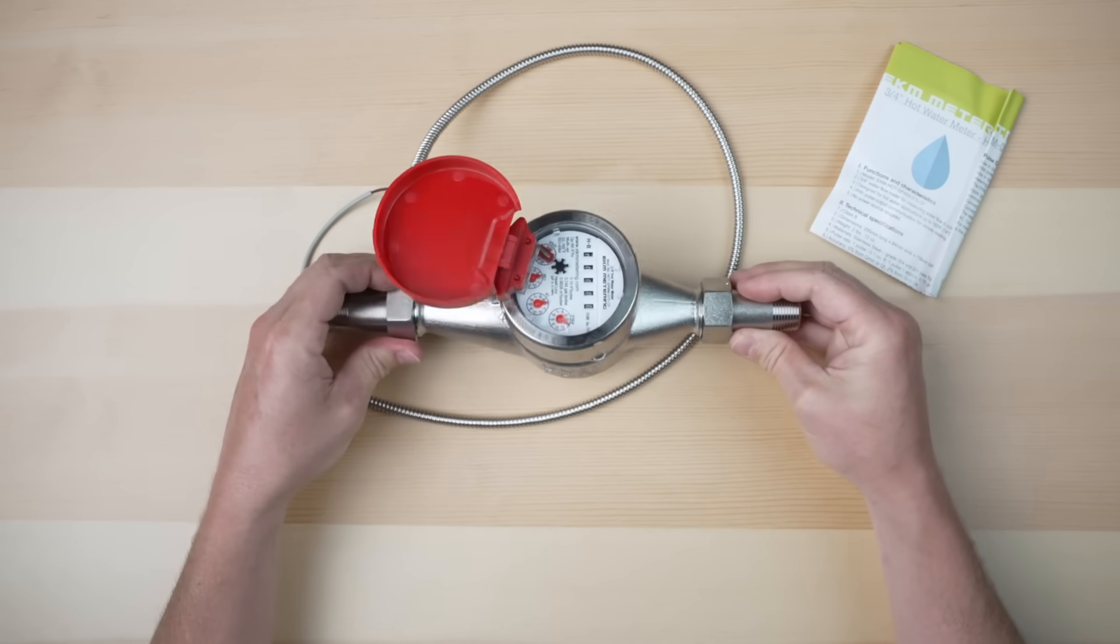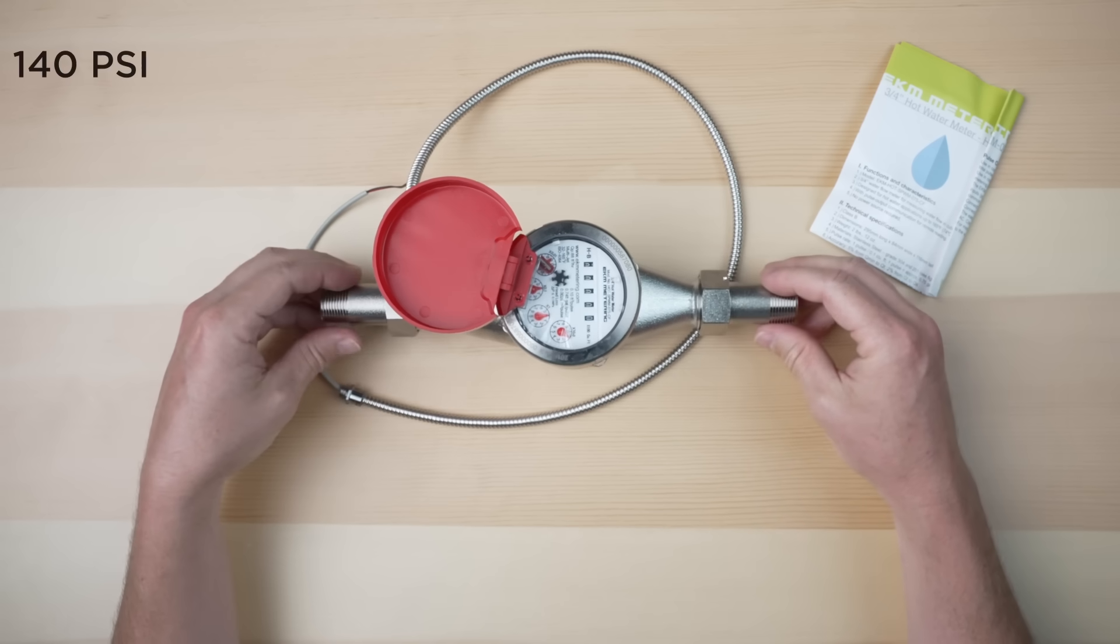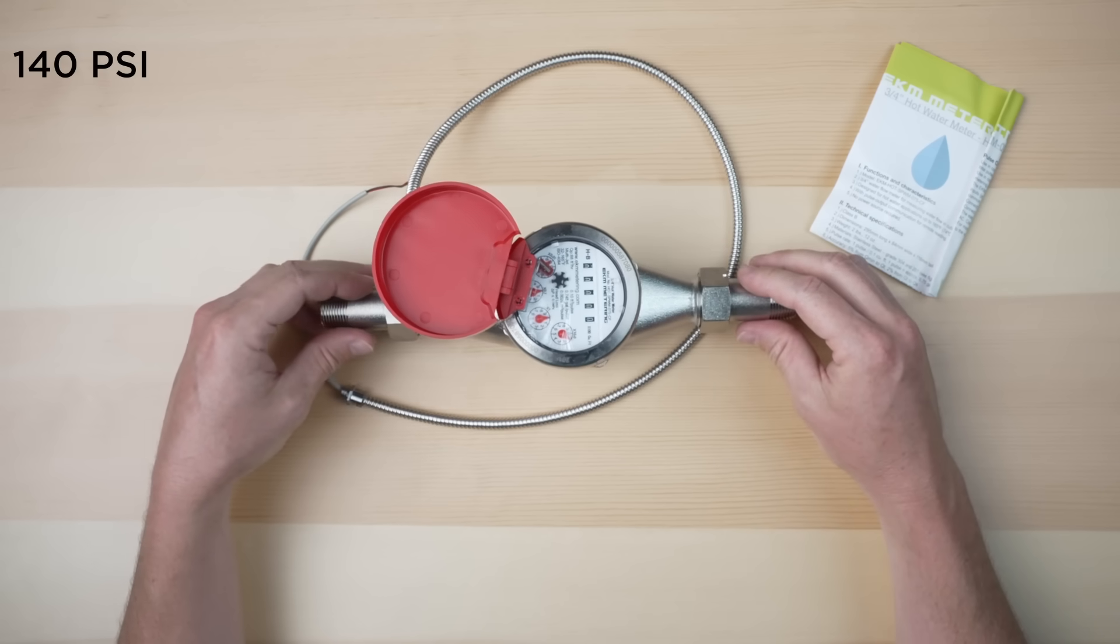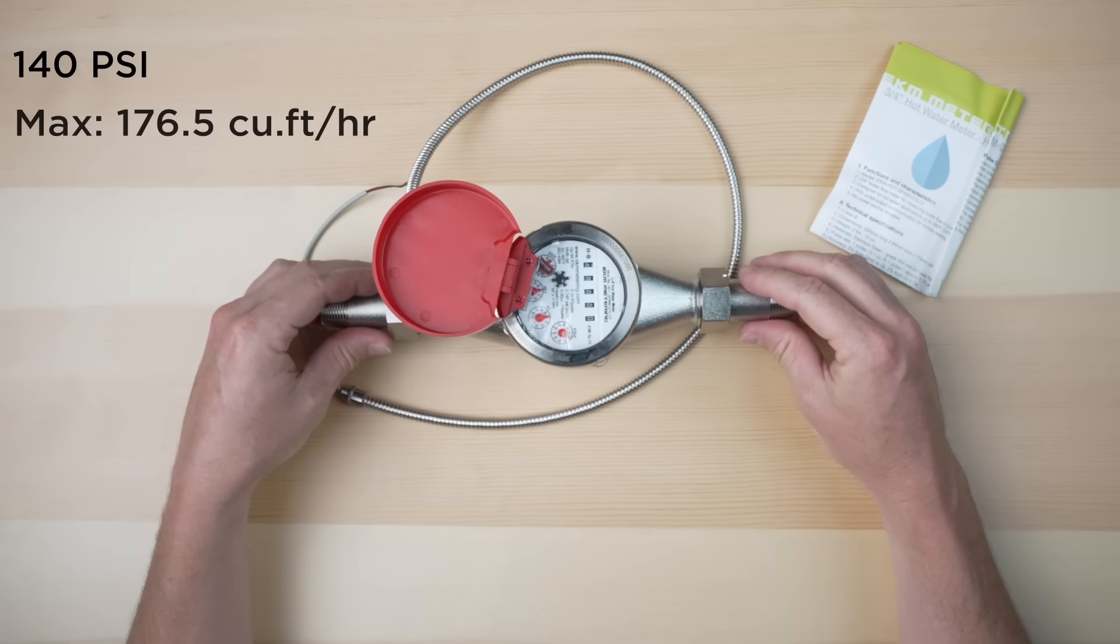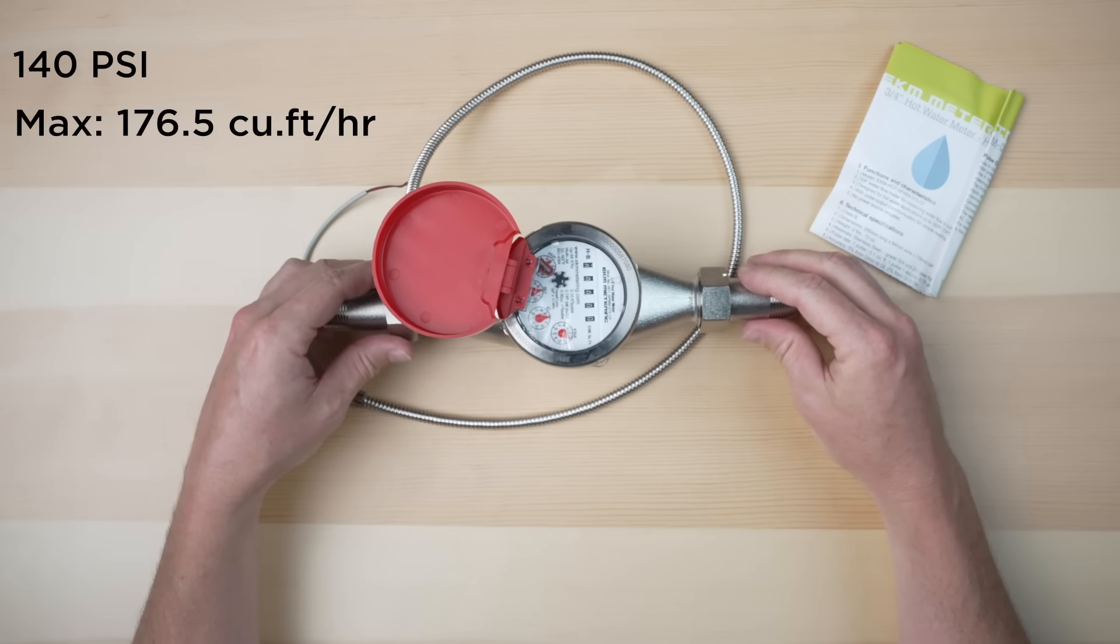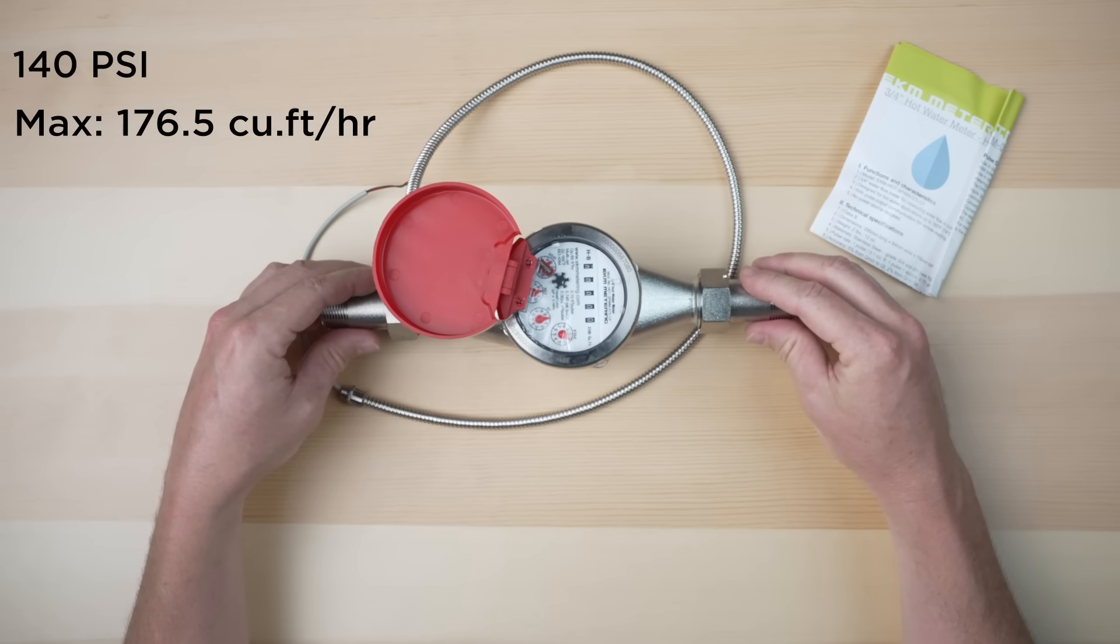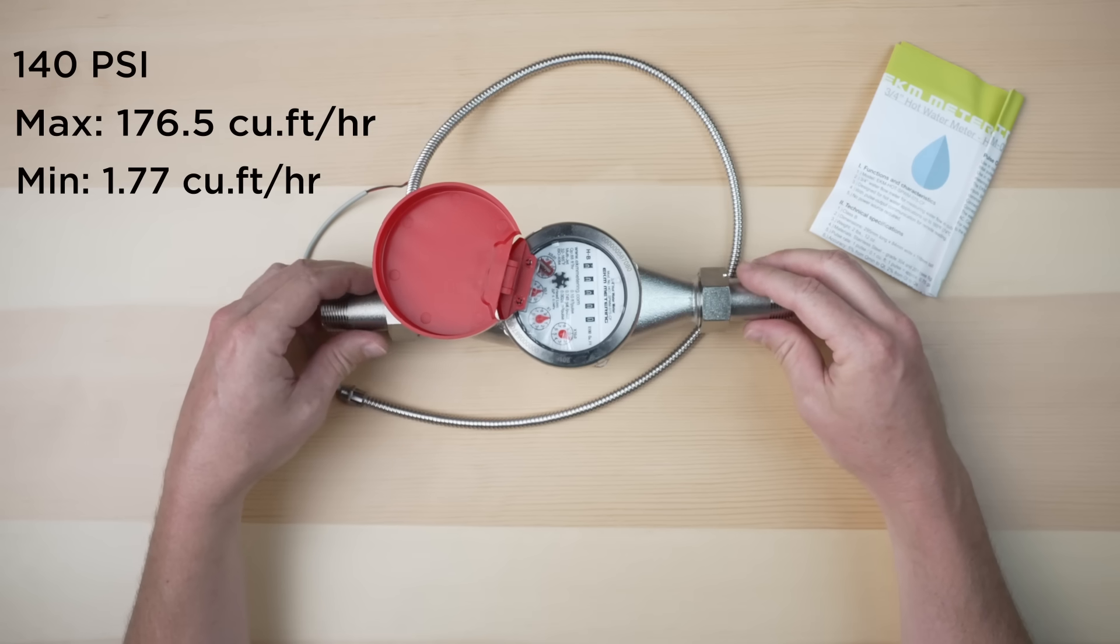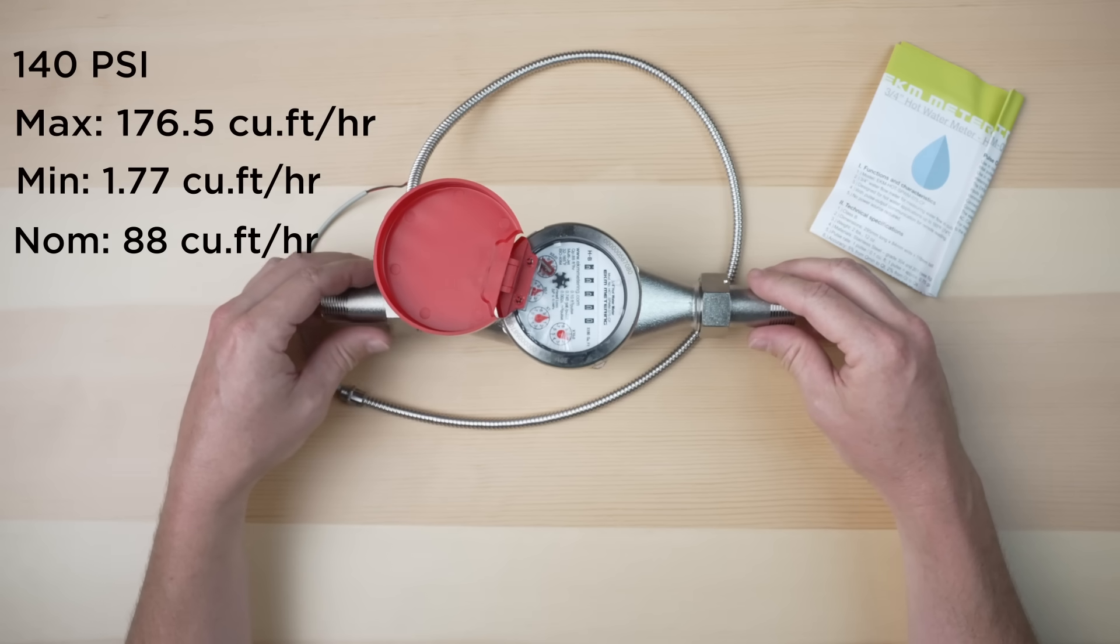The max operating pressure is 140 psi. The max flow rate is 176 and a half cubic feet per hour. The minimum flow rate is 1.77 cubic feet per hour. And the nominal flow rate is 88 cubic feet per hour.